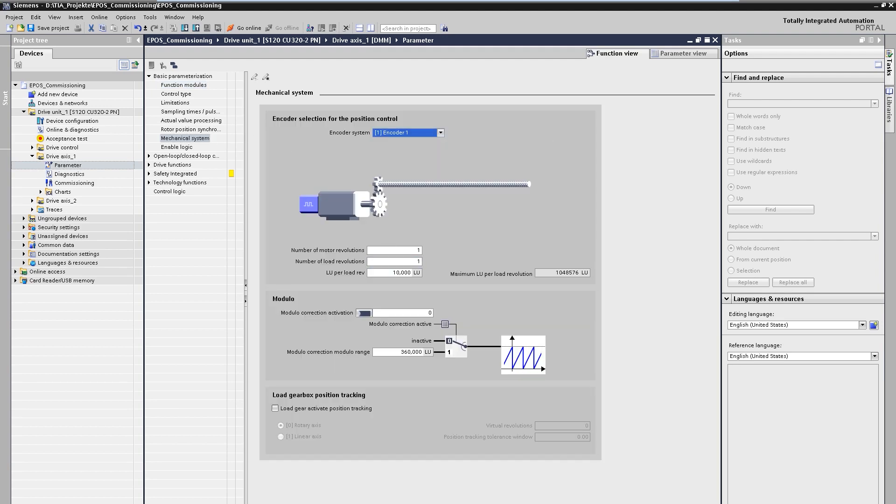Now a new mask appears in which we can define the mechanics. Here, we can for example specify the transmission ratio of the possibly existing gear and the resolution of the position values. Common applications for linear movements, for example, are realized using spindles, whose pitch could have a value of 10 mm per revolution. The preset values would fit this mechanics without gearbox with a position resolution in micrometers.